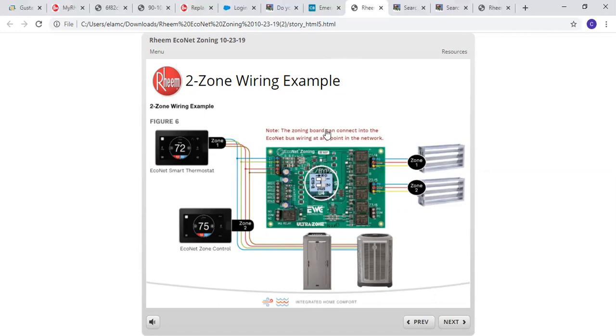And then, like I said, the biggest thing is the zoning board can connect anywhere at any point on this network. But it is important. You have your 2 endpoints, and everywhere else has to be daisy chained. So if you're going to do a 3 zone, you got to come in here, 4 wires in, 4 wires out, daisy chain to the end. It is important, which we'll get into a little bit.